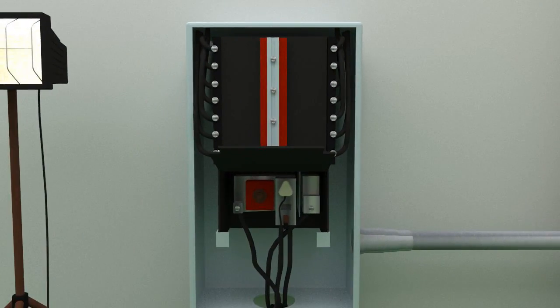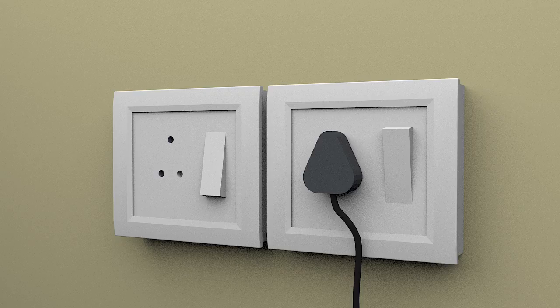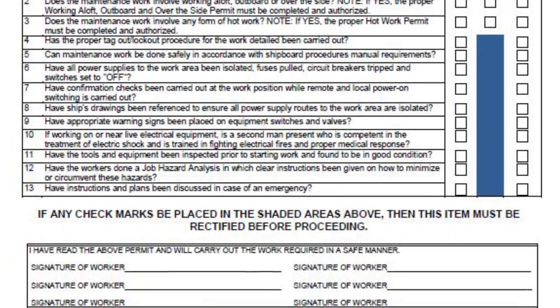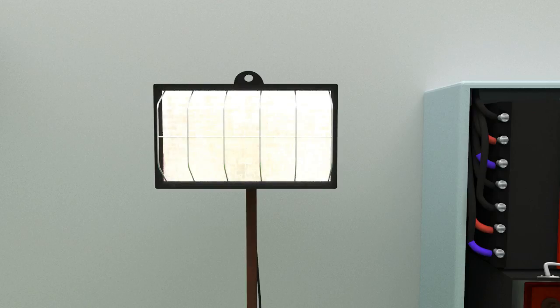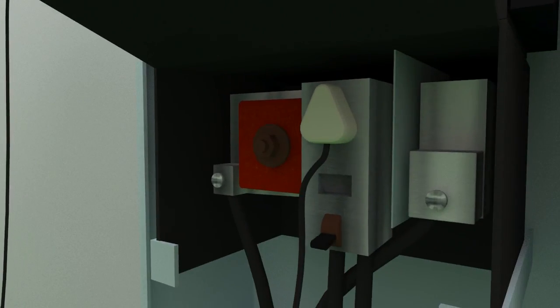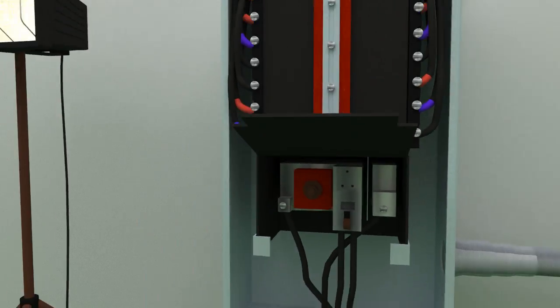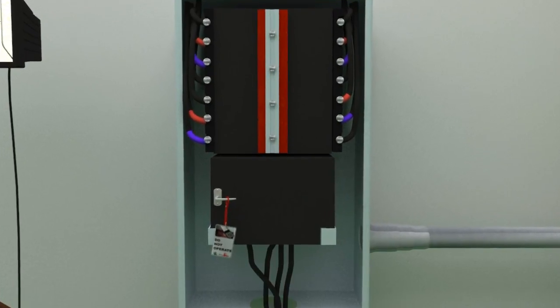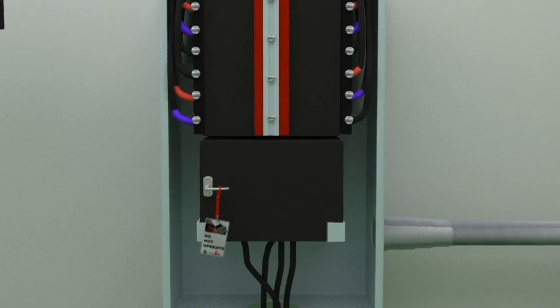Electricity can be the cause of an incident. Electrical appliances must be switched off and isolated before starting work on or near electrical equipment. Fill out the lockout tagout form and get approval from authorized personnel before starting the job. Then: turn off the equipment, disconnect the circuits from the power source, lock out the energy sources, place a tag on each lock, and test to make sure the instrument is locked out and tagged out.